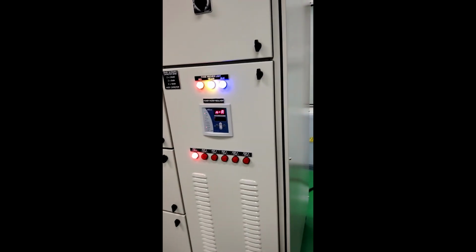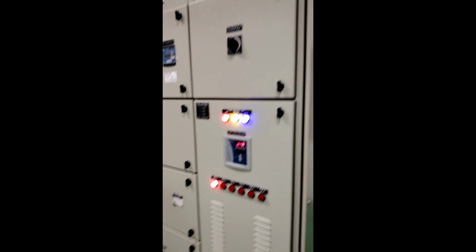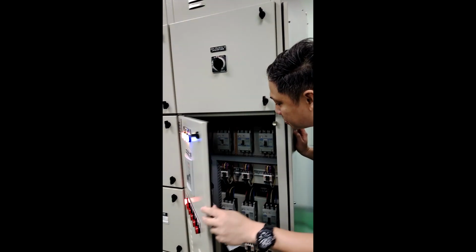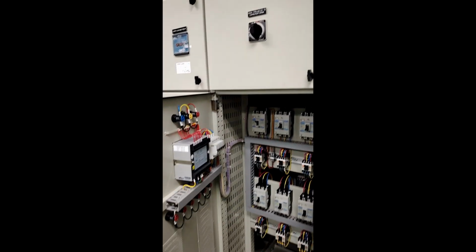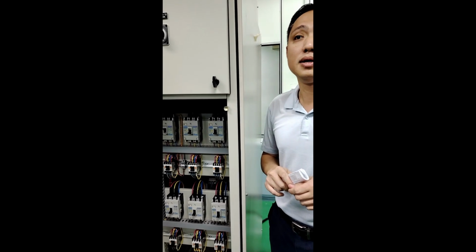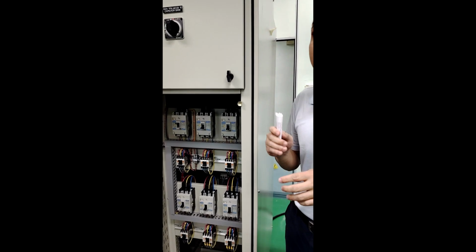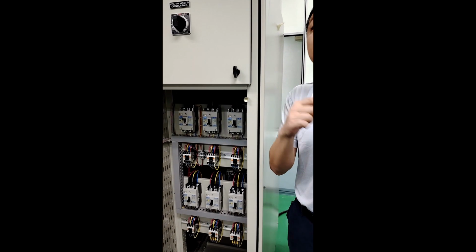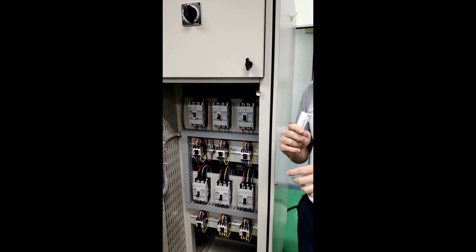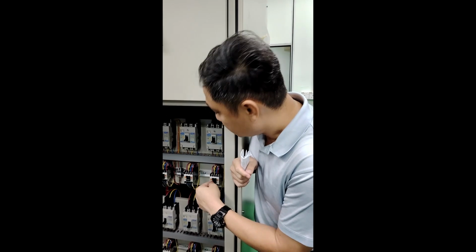Okay, now define the circuit breaker of the capacitor bank. Good, I missed out that. Let's say a 2.5 kVAR step. The breaker and the contactor need to be doubled up in value. Let's say 2.5 kVAR, so 10 A. The minimum rating for the breaker is 20 A, and the minimum contactor sizing is 20 A AC.